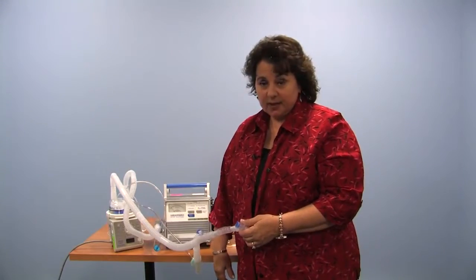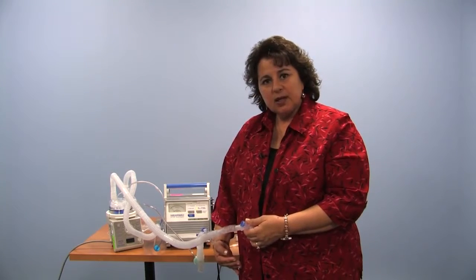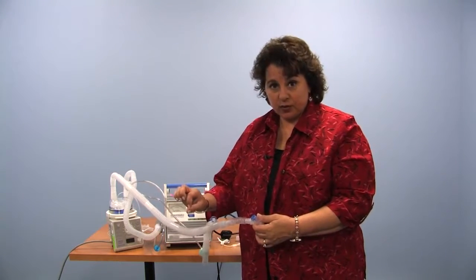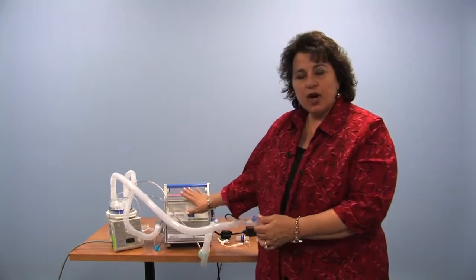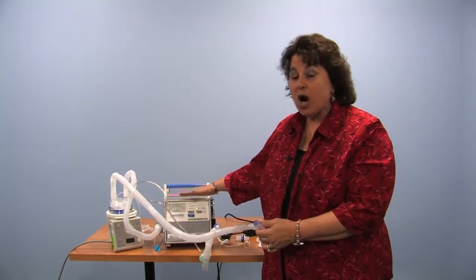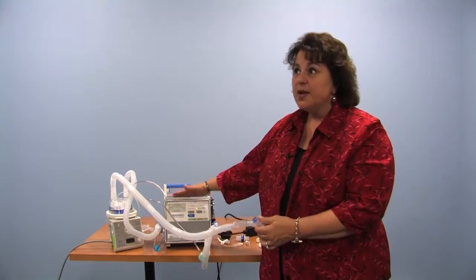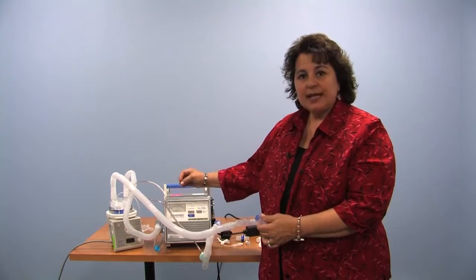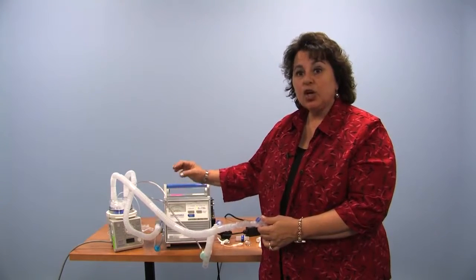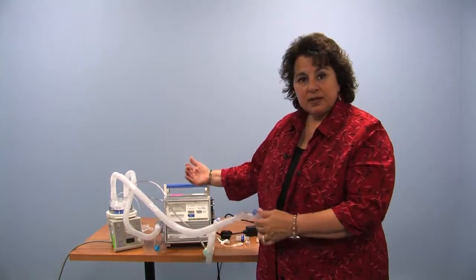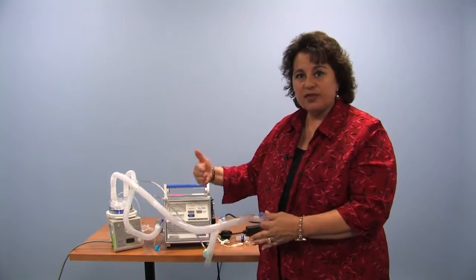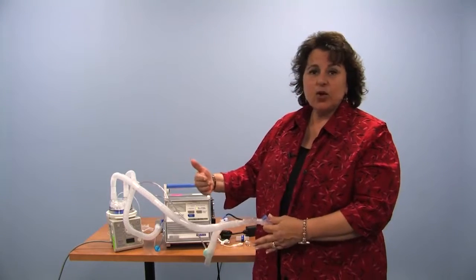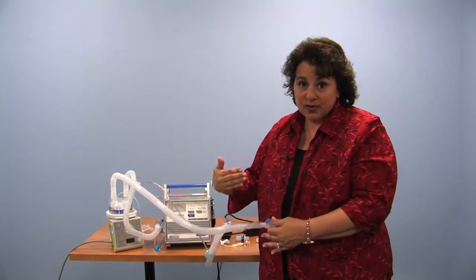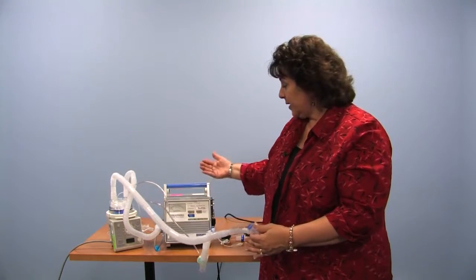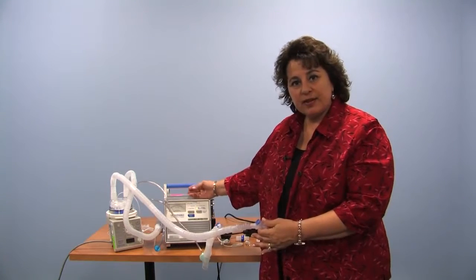The Newport HT50 in our area here in New England is typically utilized for older children. It does have larger adult ventilator circuits rather than smaller neonatal circuits. It does have some features that are not available on this particular model, the HT50, although are available on the HT70 and 70 Plus ventilators to aid young, weak children, infants with small tracheostomy tubes to breathe comfortably onto it. So there may be different reasons why you see other children of different ages with different machines and you wonder, well, why don't we all have the same thing? They don't all do exactly the same thing. This one I personally tend to use for older kids. It has the wonderful long battery life inside it rather than having additional batteries.